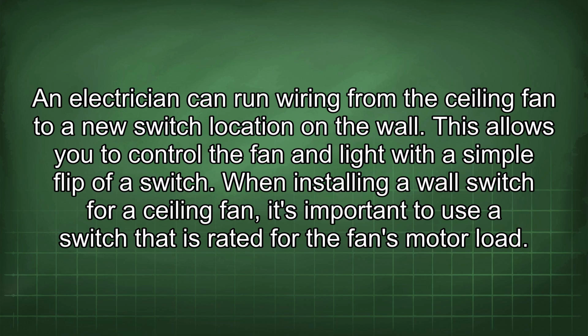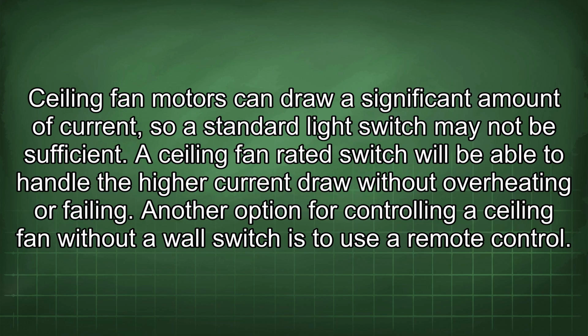When installing a wall switch for a ceiling fan, it's important to use a switch that is rated for the fan's motor load. Ceiling fan motors can draw a significant amount of current, so a standard light switch may not be sufficient. A ceiling fan rated switch will be able to handle the higher current draw without overheating or failing. Another option for controlling a ceiling fan without a wall switch is to use a remote control.